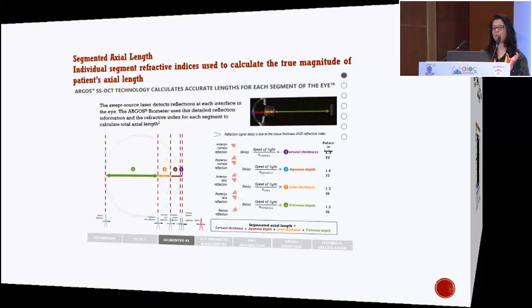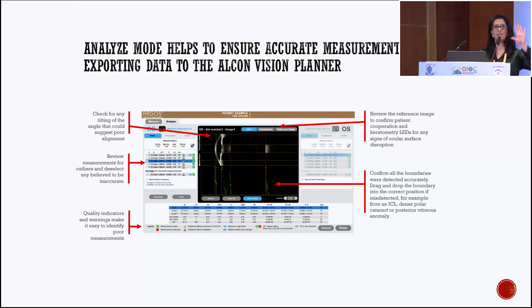The best part is the analyze mode. Once you've taken the acquisition, we train the optometrists to check every single parameter of how they have acquired the image, right from checking the head tilt, which is a parameter, then you look at your graphs, then you look at your outliers. Wherever you see that your measurements, out of the 5 measurements in kerato, if something is a 0.2 out or a 0.1 out, the machine will highlight it. So out of your 6 readings, you take away 2 and keep your 4 best to give bang on results. So at every point you can analyze and customize it.